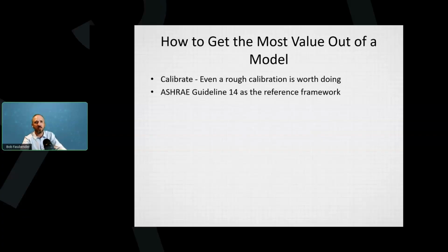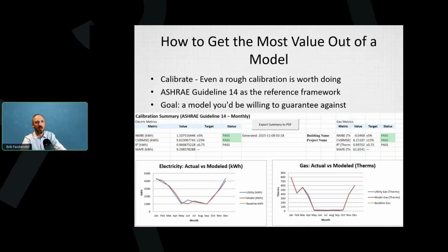If you want to get specific, there's ASHRAE Guideline 14 as a reference framework. Unless you have to model ASHRAE 14, I would use it as a guideline and not actually stick to it. Many times in my scenarios, I have to meet that, and it's a pretty tight framework. The goal is a model that you're willing to guarantee against, and so here's a picture of one that's passing ASHRAE Guideline 14. You can see it's not exactly a match, but there's a statistical regression, CV, R squared, NMBE, and those all have to be within certain thresholds. And you can see the thresholds are pretty tight from the graphs, but they are not perfect.